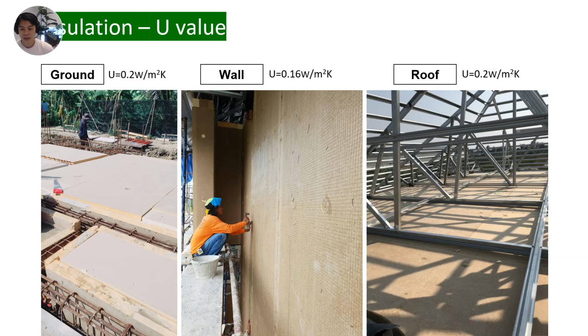First, insulation. Because of the very hot climate in Bangkok, the air temperature can make the ground soil reach 29 degrees Celsius or even higher. So in addition to insulating the roof, it was also necessary to add insulation to the walls and the ground. Second, low U value walls. Achieving a low U value in a wall is essential to reduce heat transfer.